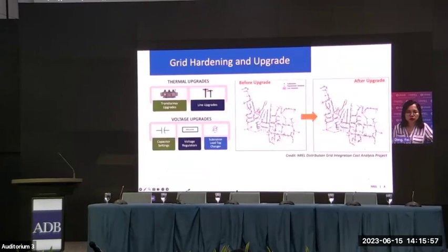So to expand the hosting capacity, we could upgrade the physical infrastructure. Thermal and voltage are the two major factors limiting the hosting capacity. So we can do upgrades on the distribution service transformers and distribution lines to expand the thermal capacity, and also add more voltage regulation devices to improve the hosting capacity.